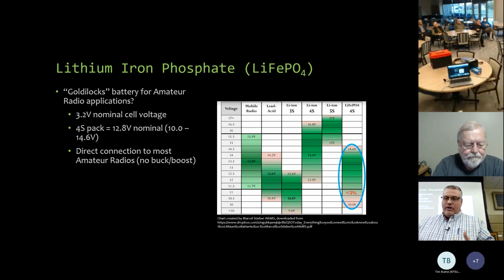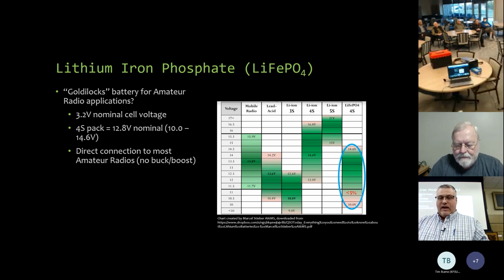If we put 4 in series, we end up with a maximum of 14.4 and minimum of 10 volts, and less than 5% of the battery's capacity is unusable—really down in that range. So it's a very close match for the lead acid batteries our equipment is largely designed around. If you match up the mobile radio, it overlaps nicely with the lithium iron phosphate battery.